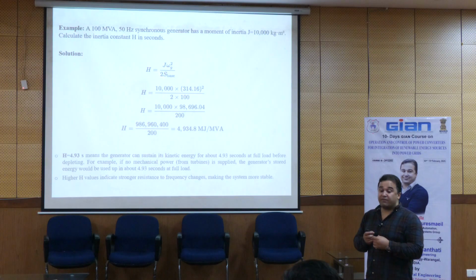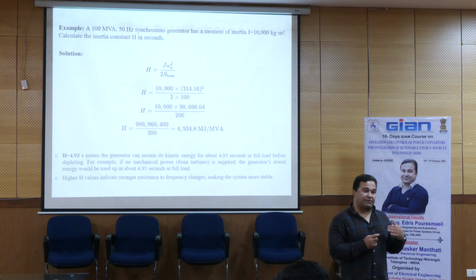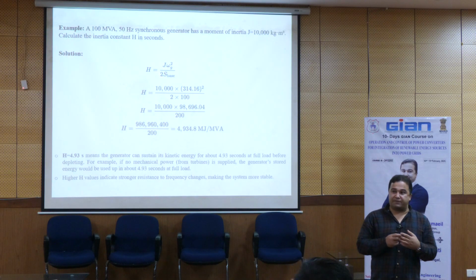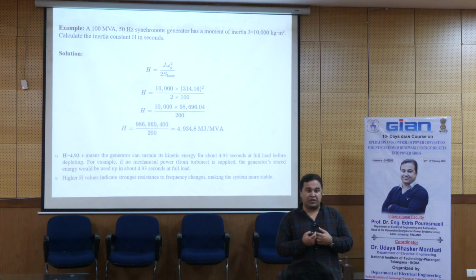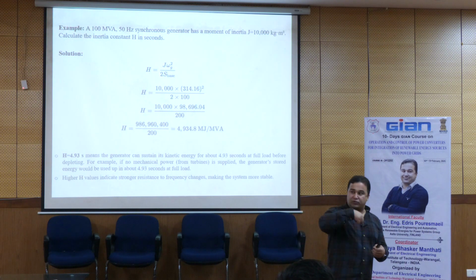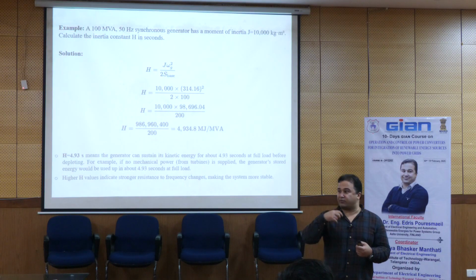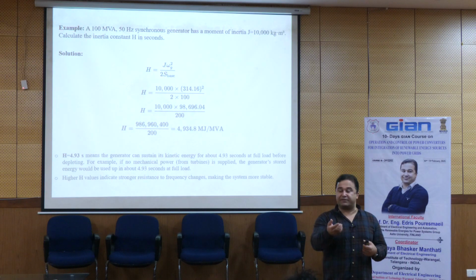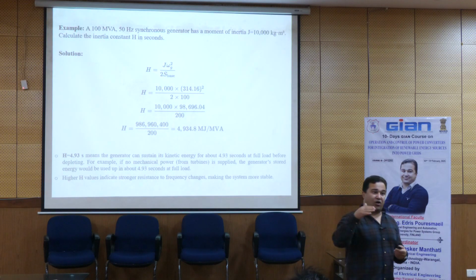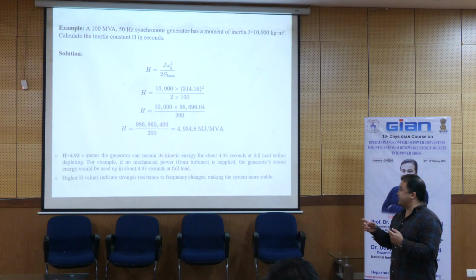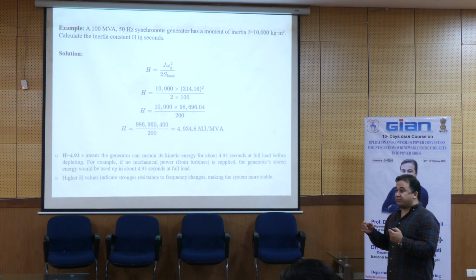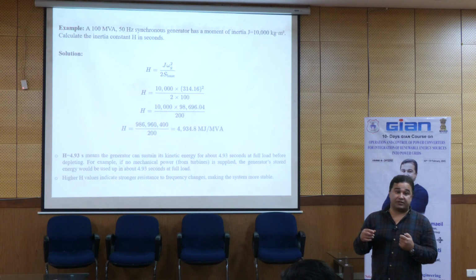So when we get back to the power system and a fault happens, if we had such a case like this type of generator, you have 5 seconds for the governor to detect the frequency, provide the right value, and then give it to the other generators to go upper. So after close to 5 seconds, some problem happens for the power grid.